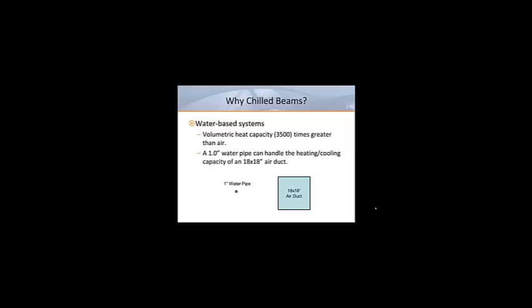Water is a far more efficient way to transport thermal energy. Since the volumetric heat capacity of water is about 3500 times greater than air, we can use a water line to replace a much larger duct. In fact, a one-inch water pipe can handle the heating and cooling capacity of an 18 by 18 inch air duct.